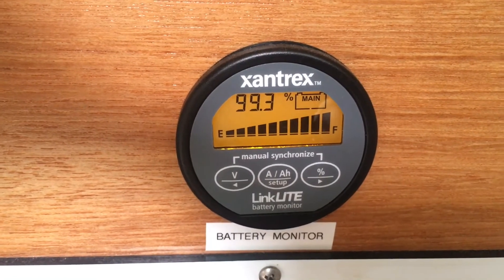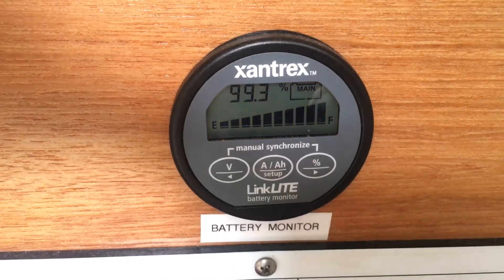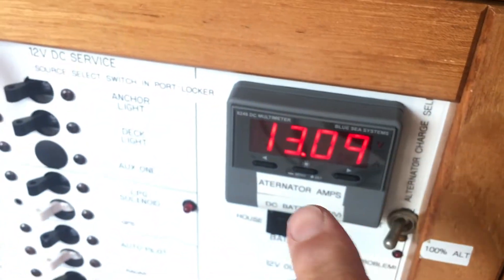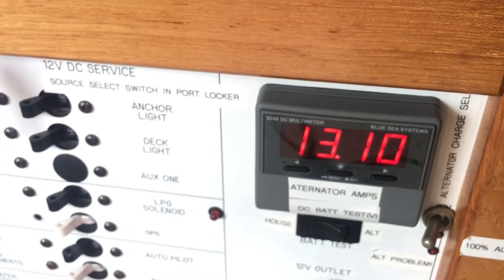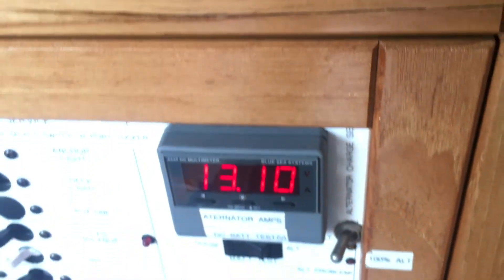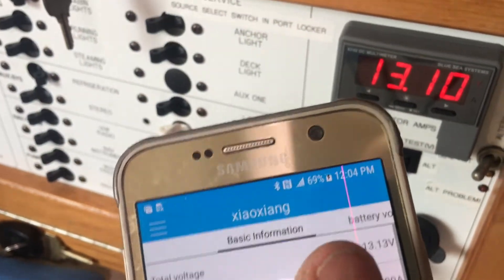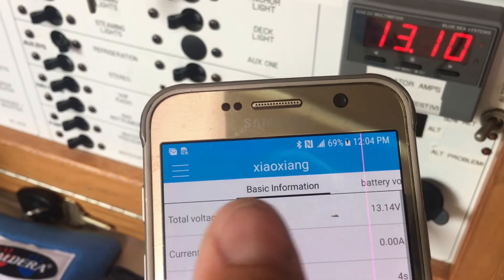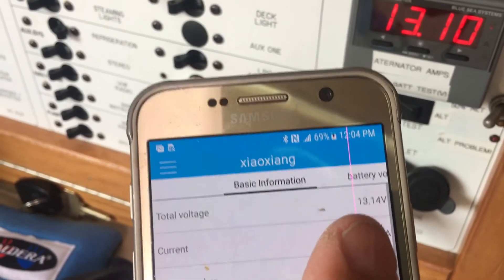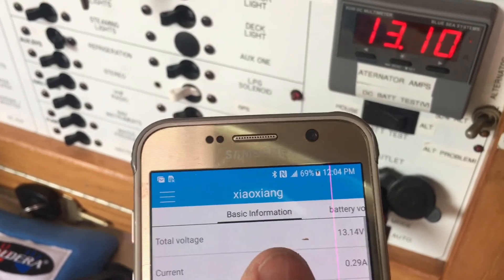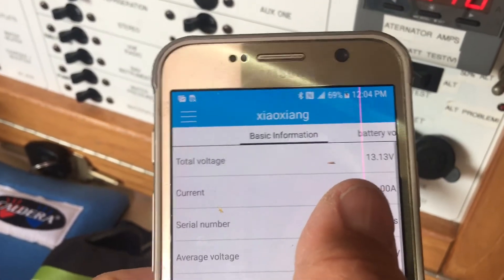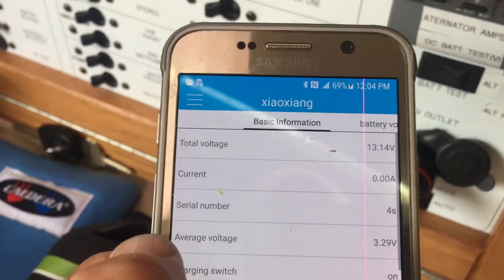This is not for charging, though. I think charging would be another possible problem. You don't want to charge the lithium with a lead-acid charger. The lead-acid battery can be charged at 14 volts, but lithium batteries don't like to go to 14 — I take my lithium battery to 13.8. On solar, I would set my charging limit to 13.8, and I would not run a lead-acid charger on these battery banks when they're paralleled.